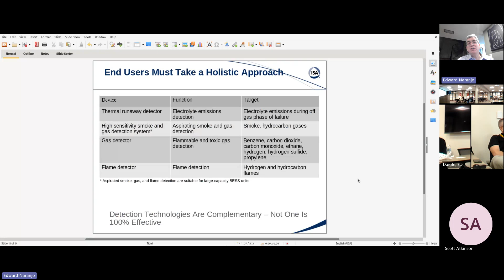So what do these systems look like? Most BESS units, unless very large, have very little space for sensors. Typically, one would have a control system that could manage a number of container units, shown in the upper left of the slide. Inside the containers, you could have a thermal runaway detector—I've shown a Li-ion Tamer, a specific brand. You could have high sensitivity smoke detection systems where the box is either inside the container or just outside, with only the sensors inside. Gas detectors and flame detectors are also quite common; these can be small and provide adequate coverage for most installations. And of course, beacons and sounders, typically installed outside these units.